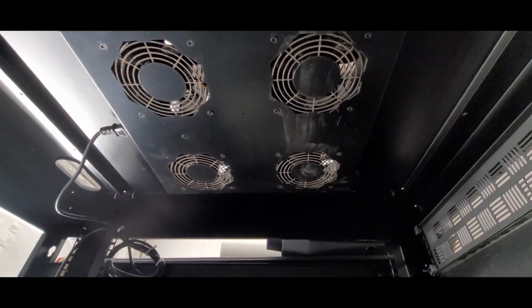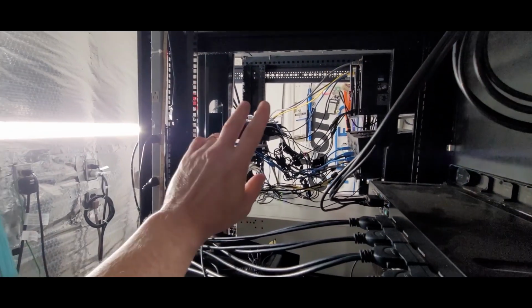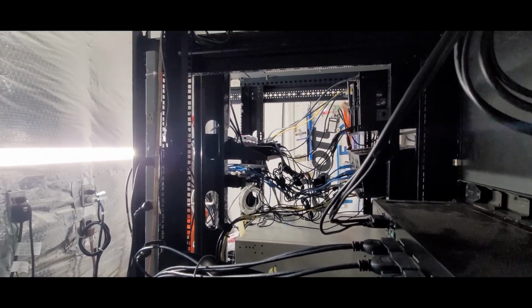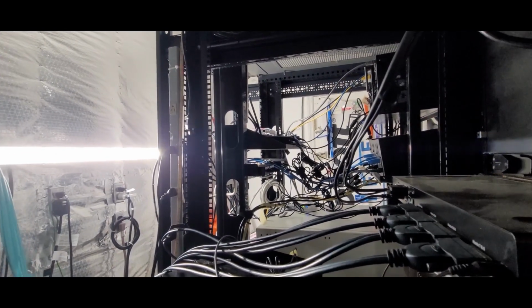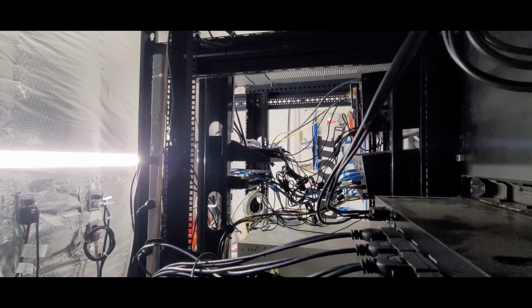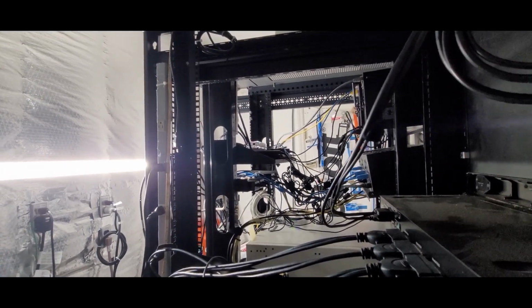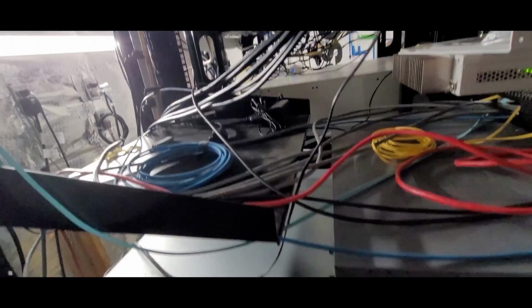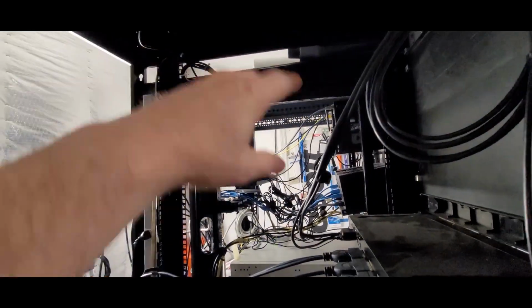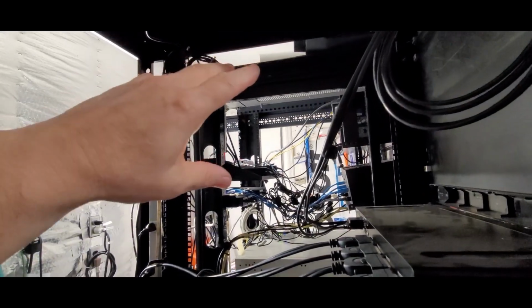Now, I can't have the wall frames on these racks because that creates what we call the tornado effect of heat. The tornado effect of the heat means it's allowed to multiply its degree because the accumulation of heat is greater than the cooler air that comes through the system. And as you can see, I've got fairly big gaps here, and therefore this space right here would have become a very hot zone very quickly.